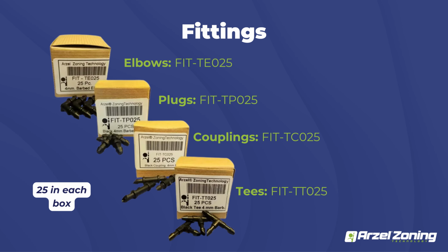As far as fittings go, we have a number of different fittings. So we have our T's in the bottom there. That's going to be your most common fitting. Anytime you guys are doing branch style ductwork, you're going to end up using the T's. And basically every damper that's on one individual zone just gets teed off of the main line, leaving the panel. Like I said before, you don't need hose clamps or anything. They're barbed fittings. They just slip right into your tubing.